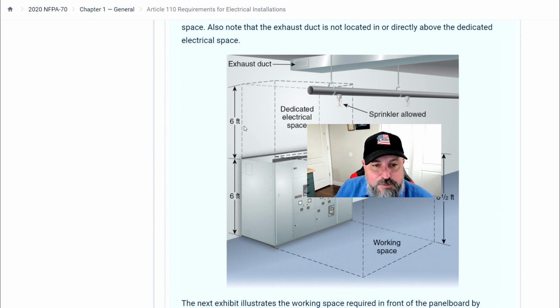So here's the big example. All this space up here is your dedicated electrical space. And during my inspections, I've actually caught a couple of times where the plumbers have run straight over this space and right over our equipment in that space. And they had to change it. They had to move their pipe. They are not allowed per code to go into that dedicated space, right? So no air ducts, no exhaust ducts, anything 6 feet above the equipment and the same depth as the equipment, all surrounding that is not available in there.